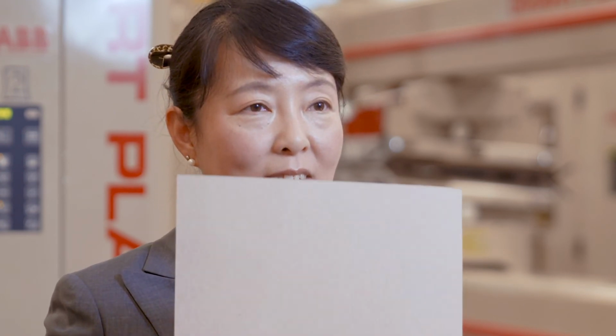For each paper mill, they have to look at what sensors they have, the locations of these sensors, and look at their process. They have to pick the sensor correlation method. For example, I want to test the moisture content of this piece of paper. I'm going to be using an oven. The oven has to be set at 105 degrees Celsius according to the TAPPI standard, and then how much drying time it's going to take. The paper maker will have a standard operating procedure for each online sensor they're going to correlate.